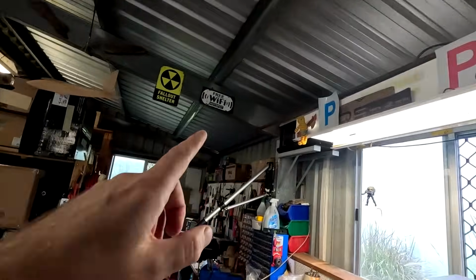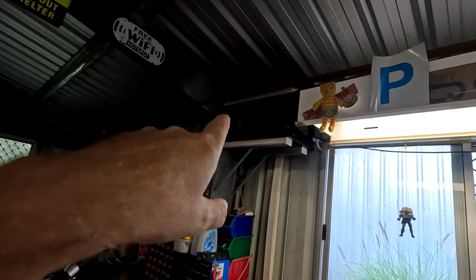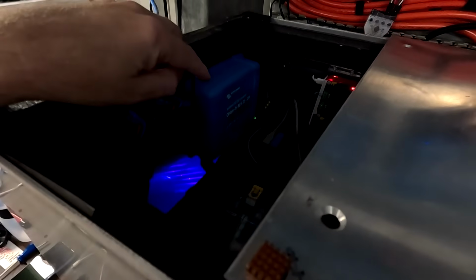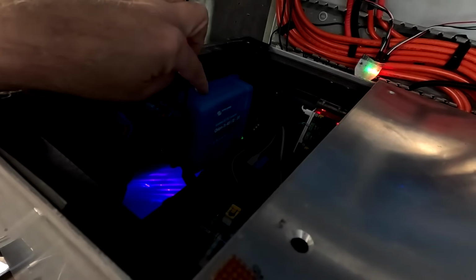I decided against another fuse or main switch for the power supply of the network cabinet up there, because the Victron DC to DC converter here is short circuit protected. That means even if we have a short on this 12 volt output, it doesn't destroy the device, it just delivers 20 amps and that's it. And we're using a 4mm cable, so there's no problem for this cable to carry 20 amps continuously.